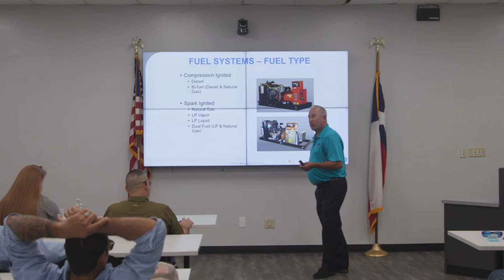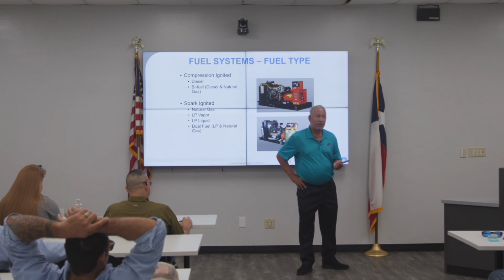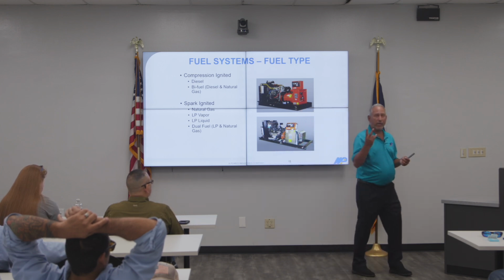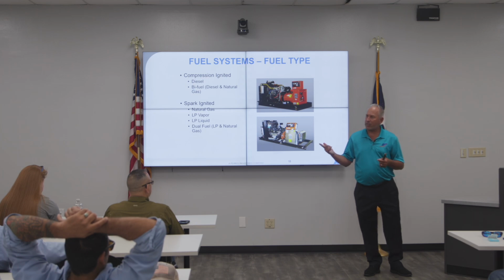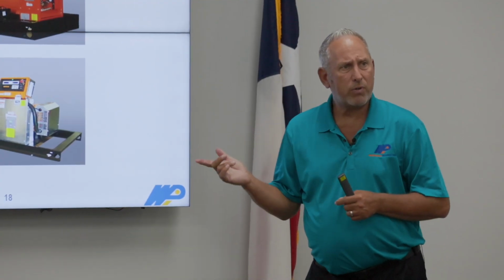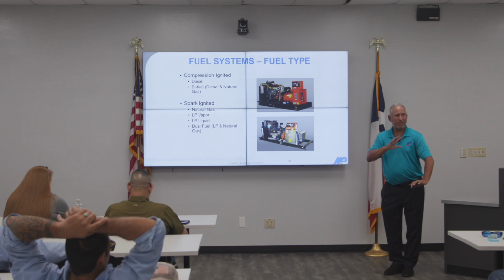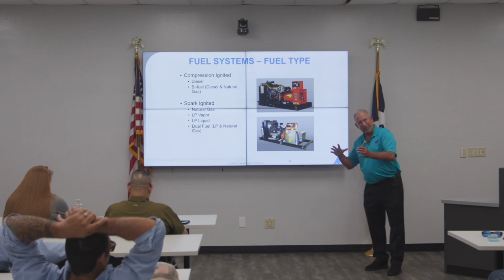There's only a couple of manufacturers today that have EPA certified units. Generac's one of them, with a 500 and 600 kW. Volvo does it themselves in a 500 kW. The reason they're doing it at that size is because of tier requirements on smaller gensets — those fuel delivery systems are so sophisticated that if you throw them off with natural gas, they get lost. So they have to go to a somewhat dumber fuel delivery system to operate better.